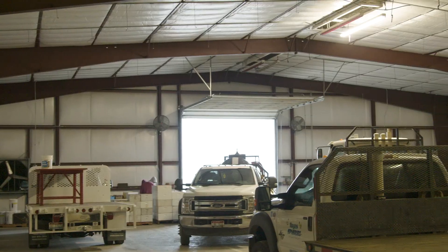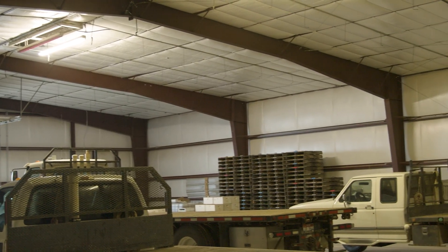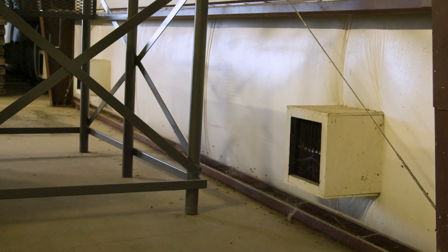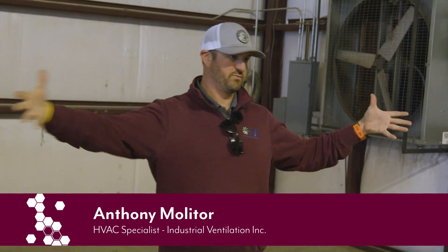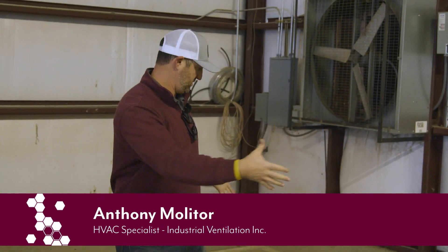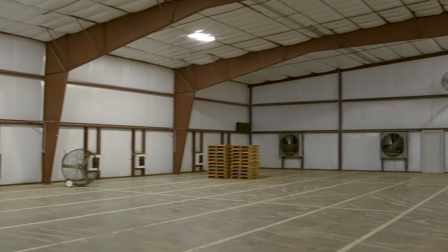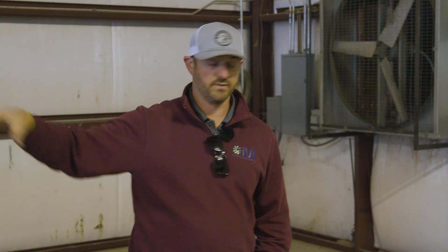This is the original bee storage we built in 2006. It's basically designed for positive pressure — you're sucking in more air than you're letting out. That's based on what other beekeepers in this valley have done, retrofitting buildings. With positive pressure, you basically shouldn't have any hot spots because you can guarantee where the air is going. With the small exhaust boxes under positive pressure, if you have exhaust there, that's where the air has to go. If you just did a full sweep with one intake and one exhaust, it'll migrate slowly and you'd have pockets in the corners that could get hot because you're not guaranteeing where the air is going.